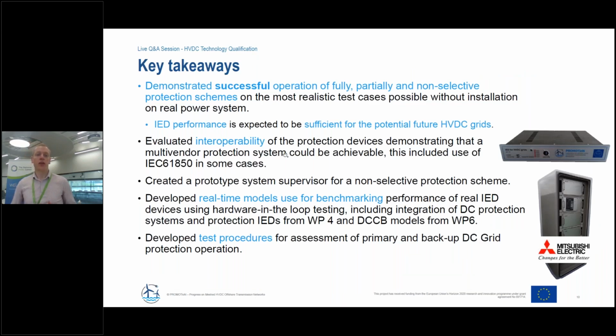So the key takeaways are that we demonstrated successful operation of fully, partially, and non-selective protection schemes - all the options - using the most realistic test cases possible without actually putting it on the real system. Throughout it all, the IEDs performed as you would expect, and it would be sufficient for use on the future HVDC grid. You can see a picture of the two IEDs that were used for the partially and fully selective testing on the side.